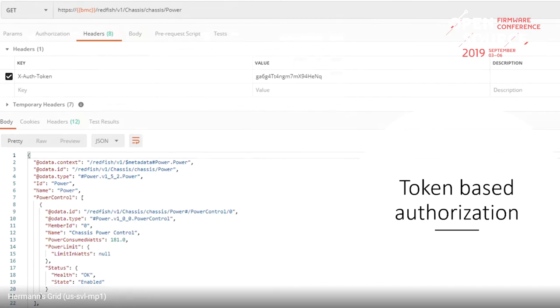Token-based authorization is recommended if you're going to do multiple calls. This requires the client to POST to the sessions collection with their username and password to get a token. You can POST to /redfish/v1/SessionService/Sessions unauthenticated and get the token if you pass a correct username and password. This is using the token to do a GET to the power schema — you can see things like power limit and power consumed watts.